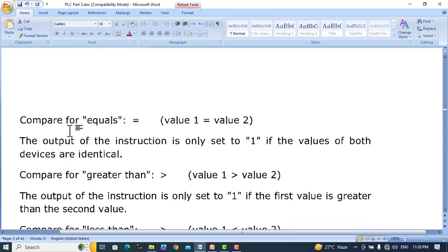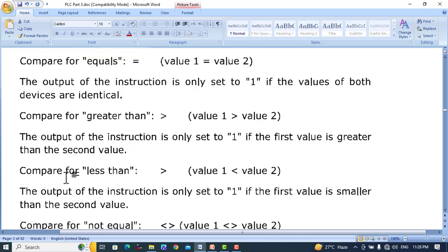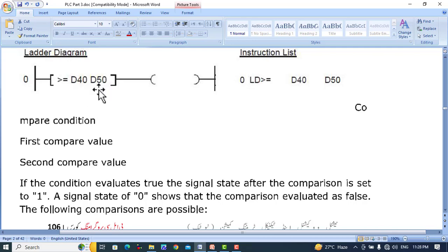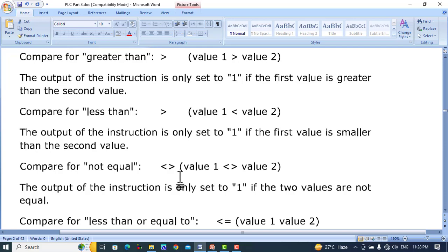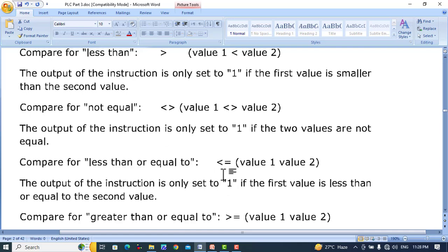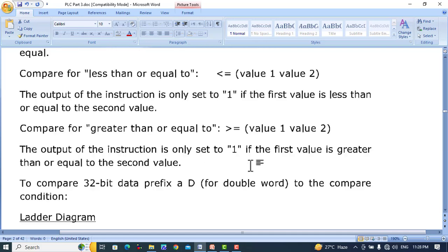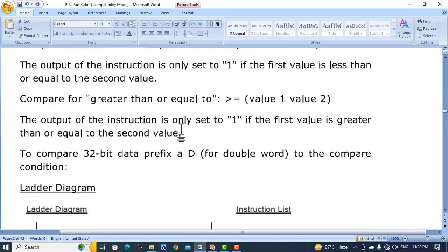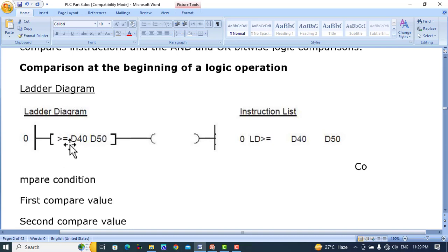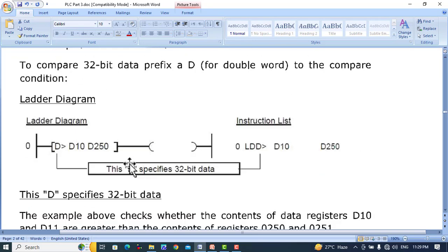We can use comparison operators individually: equal to, greater than, less than, not equal to, less-than-or-equal-to, and greater-than-or-equal-to. The first value is value one and the second is value two. For not equal to, both less-than and greater-than conditions are combined. These are 16-bit instructions; the output is set to one only if the comparison condition is met. To compare 32-bit values, add 'D' before the comparison operator — for example, D>=, D<, D>.